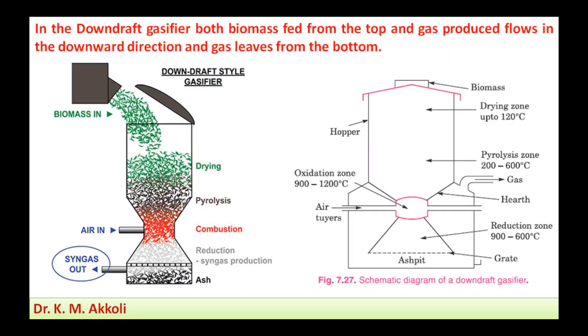Now we will take the downdraft gasifier. In the downdraft gasifier, both the biomass fed from the top and the producer gas flow in the downward direction — that's why it is called a downdraft gasifier — and gas leaves from the bottom. In this commonly used sketch, biomass is fed from the top and passes through the different zones.